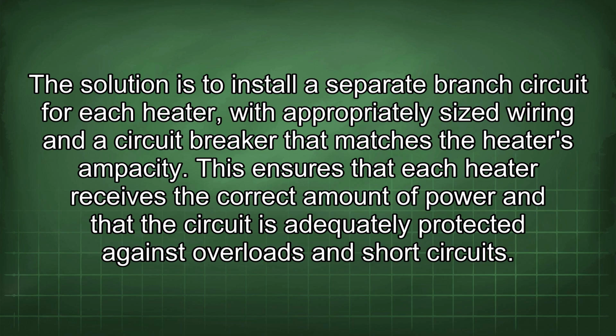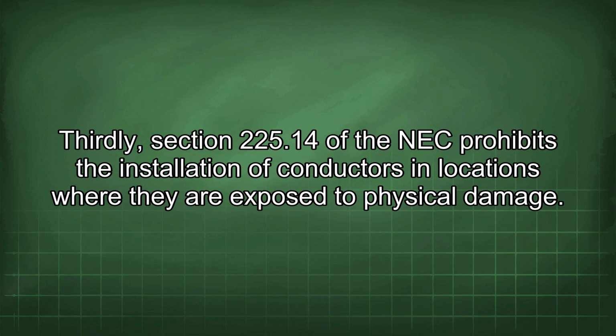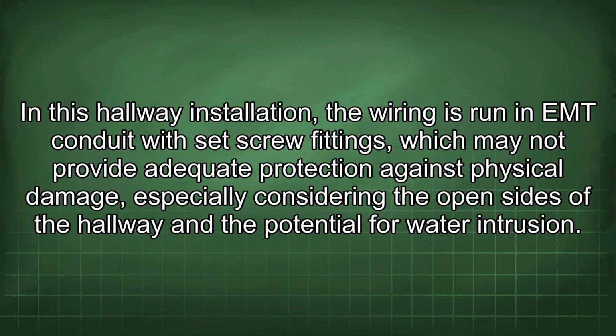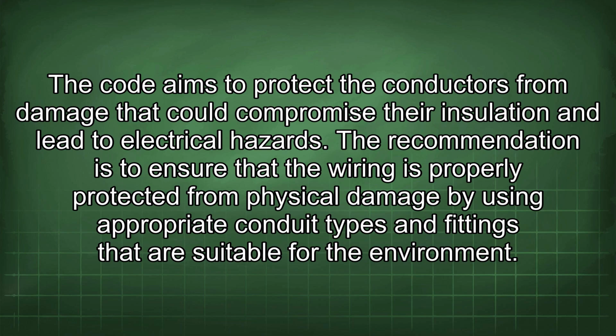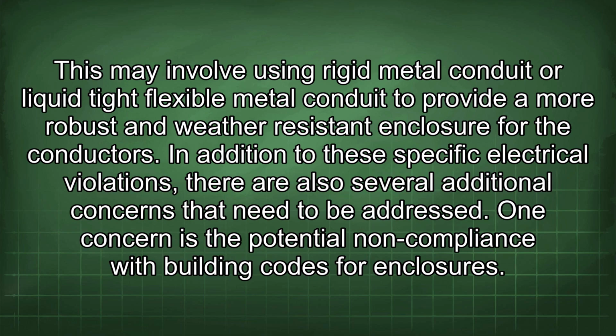Thirdly, Section 225.14 of the NEC prohibits the installation of conductors in locations where they are exposed to physical damage. In this hallway installation, the wiring is run in EMT conduit with set screw fittings, which may not provide adequate protection against physical damage, especially considering the open sides of the hallway and the potential for water intrusion. The code aims to protect the conductors from damage that could compromise their insulation and lead to electrical hazards. The recommendation is to ensure that the wiring is properly protected from physical damage by using appropriate conduit types and fittings that are suitable for the environment. This may involve using rigid metal conduit or liquid-tight flexible metal conduit to provide a more robust and weather-resistant enclosure for the conductors.